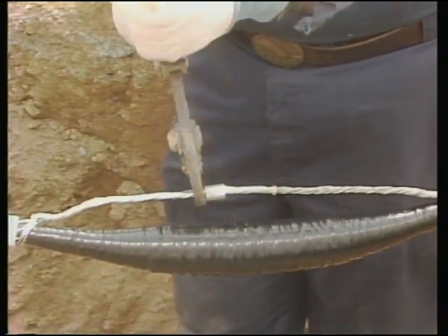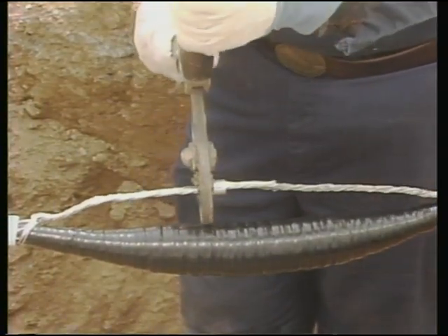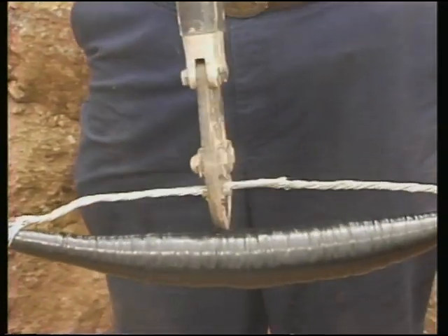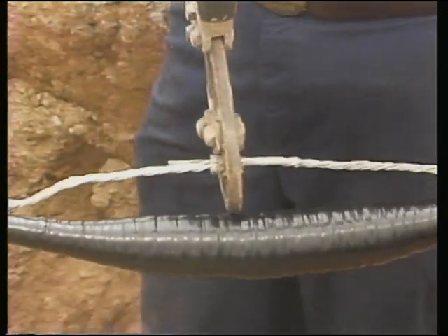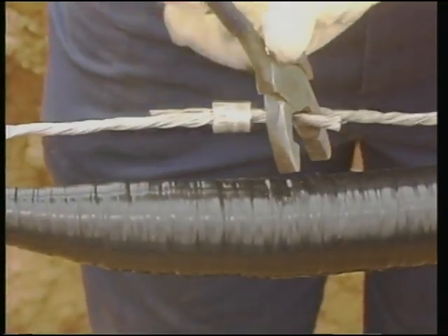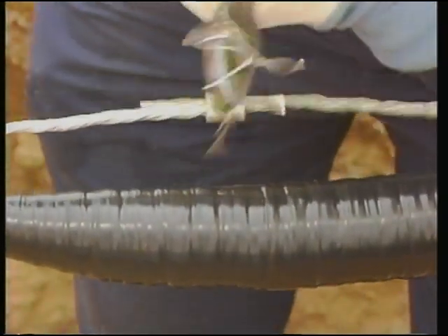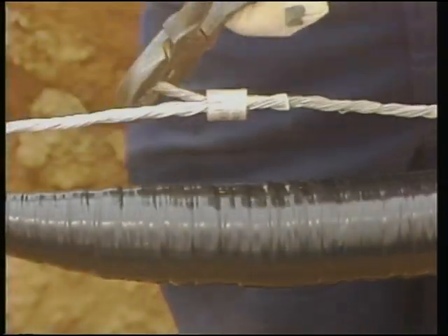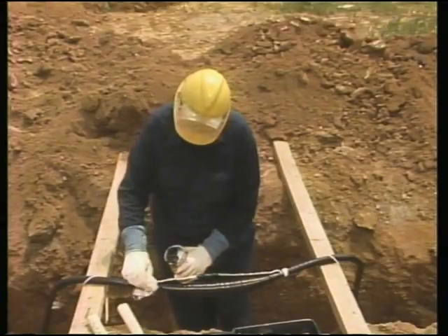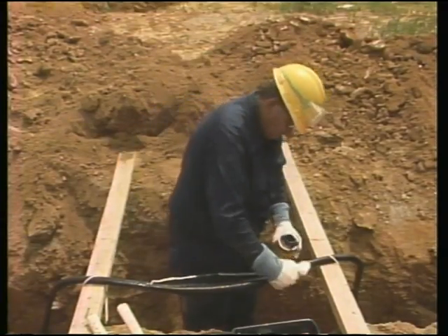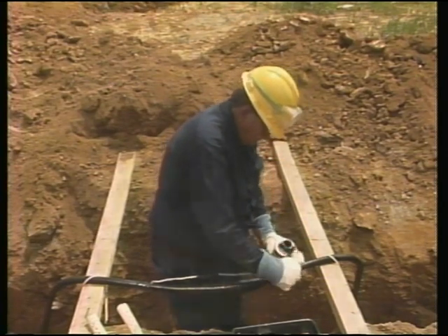A compression connector is used to join the concentric wires together. Again, instructions should be checked for the correct press and die and for the number of necessary compressions. After the compressions are made, the ends are trimmed and then taped to protect the splice area from any sharp edges. Next, the workman applies a coat of rubber cement to seal the ends and to help keep out water.